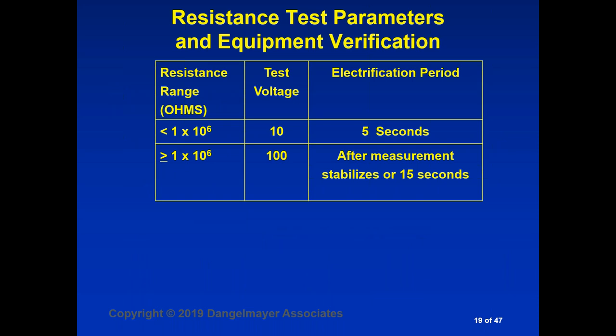Now, let's talk about the resistance test itself. For any resistance where you're measuring a surface, there's a period of time called the electrification period where the actual measurement needs to settle down. Now, if the resistance is fairly low, in the range less than 10 to the sixth ohms, the test voltage will be 10 volts. And it'll take about 5 seconds is the general electrification period. So you wait 5 seconds before you record your measurement.